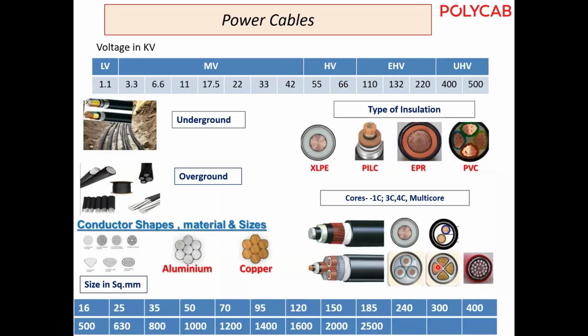Before understanding the cable accessory, we should understand the cables also. Once we understand the cables, we can better understand the cable accessories. So in this slide, we will just see a glimpse of power cables. Generally, cables are categorized as low voltage, medium voltage, high voltage, extra high voltage, and UHV, ultra high voltage. So we categorize cables depending on the voltage class. Low voltage is 1.1 kV, medium voltage 3.3 to 42 kV, high voltage 55 to 66 kV, extra high voltage 110 kV to 220 kV, and UHV, ultra high voltage, 400 to 500 kV.